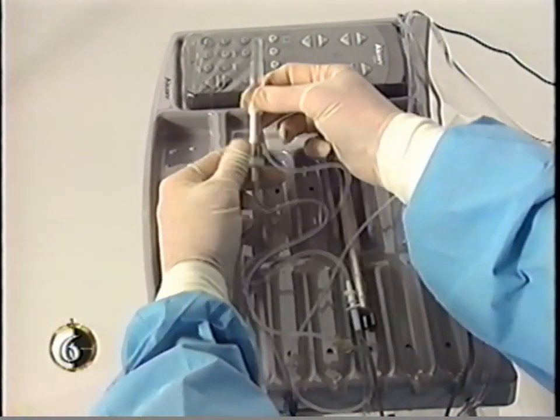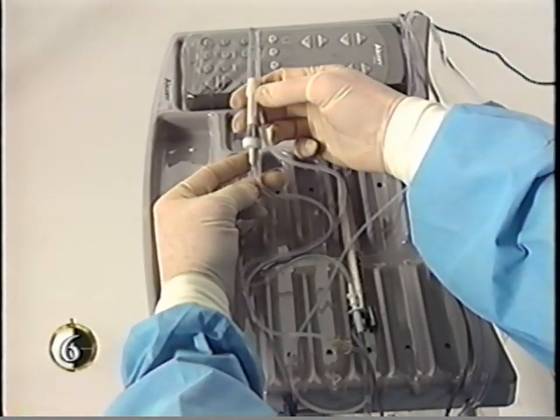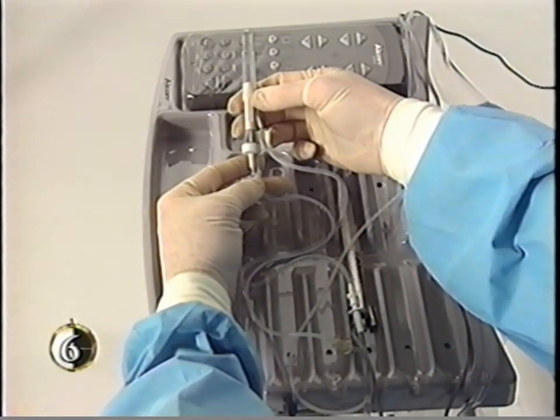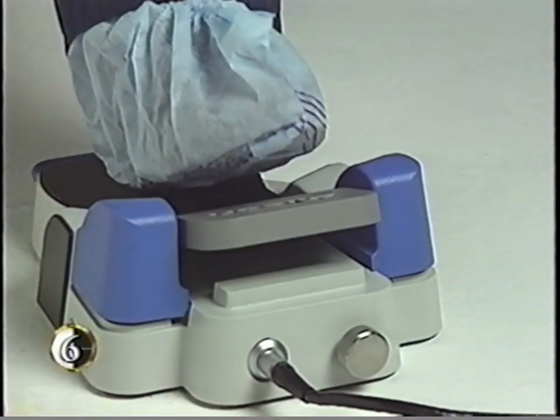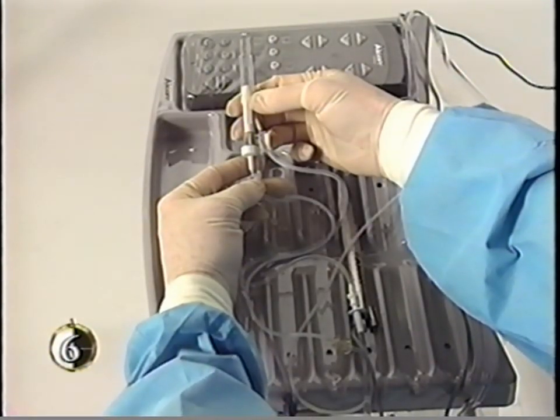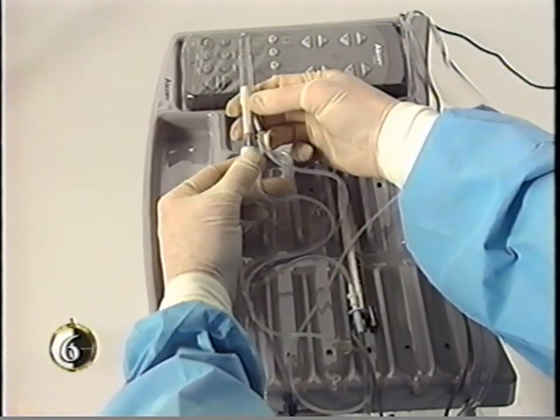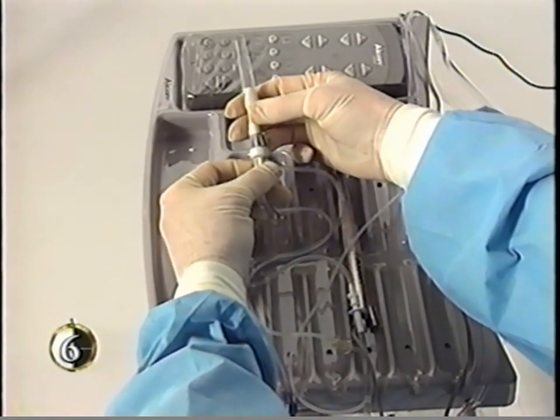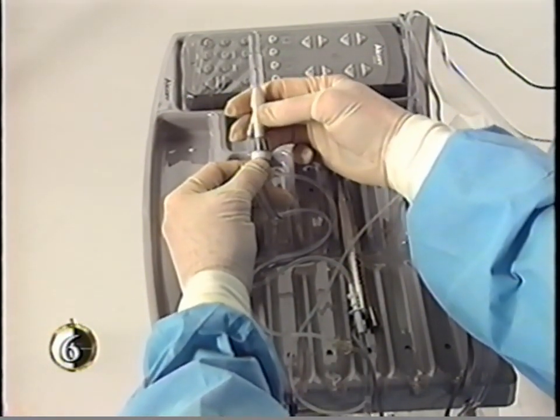The test chamber should maintain its shape or dimple slightly. After observing the chamber, release the foot switch to stop fluid flow. The ATIOP handpiece is ready for surgery. If the test chamber drastically changes shape, check the troubleshooting section of the operator's manual.